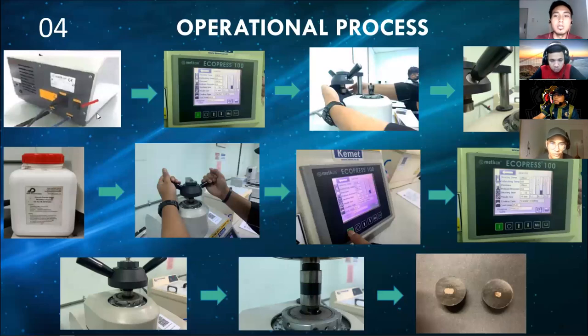We go to the operational process. Firstly, switch on the machine, then set the parameters and set up the specimen at the machine. Place the specimen and insert the phenolic powder into the mold chamber, then close the chamber and press the green button to start the mounting process.